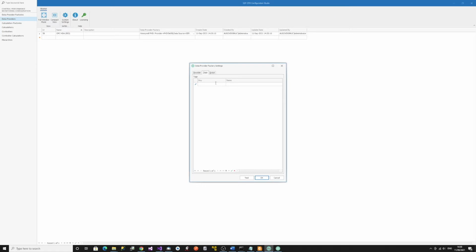Set the templates for the tags that will be retrieved for each controller. Each template needs to have an associated unique key so it can be referenced in the custom script that will consolidate these tags into a standard format. For example, some DCS vendors' PID blocks have a mode attribute, and an initialization flag to determine if the downstream block is in cascade. These three tags can be consolidated into a single mode string, for example auto operator. This will be seen in more detail later.